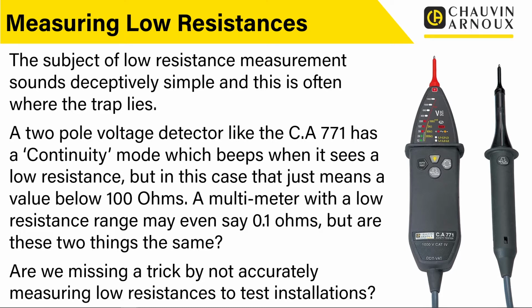A two-pole voltage detector like our CA 771 has a continuity mode, which beeps when it sees a low resistance. So continuity is often a term that we use, sort of interchangeably for low resistance, but it's not actually the case, because as you can see here, when it beeps, it sees a low resistance, but in this case that just means that it's a value below 100 ohms. So actually it beeps, we think, yep, that's a continuity reading, that's low resistance, but actually that could be up to 100 ohms.